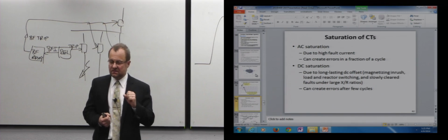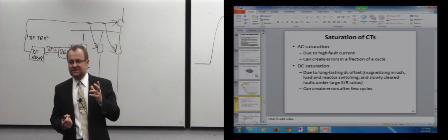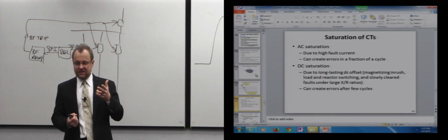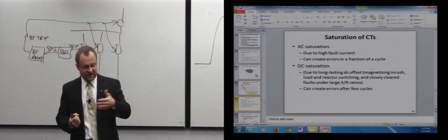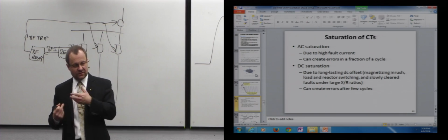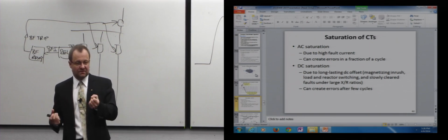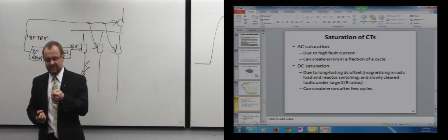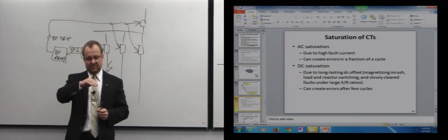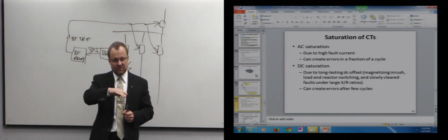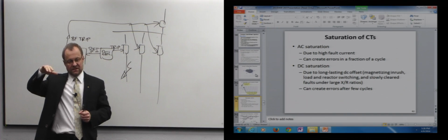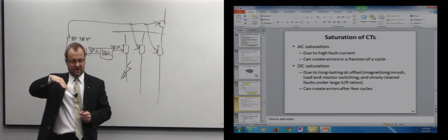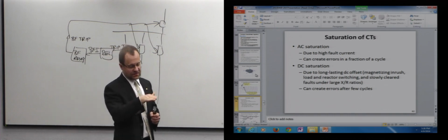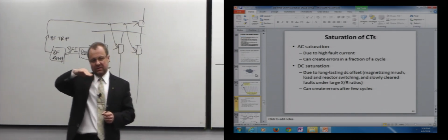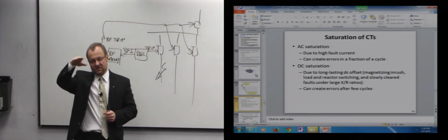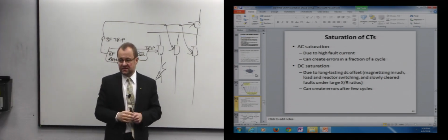And CTs, they don't like DC, right? They don't work on DC. They work on AC. It's Faraday's principle. You have to keep moving the magnetic field to induce the output from the transformer effectively, right? So if you put in a DC, the DC component of the flux will go up and up and up, because flux is an integral of the current, right? Effectively. So you have a small DC and it will get integrated up and up until it hits the saturation limit of the CT, and you start to see saturation errors.